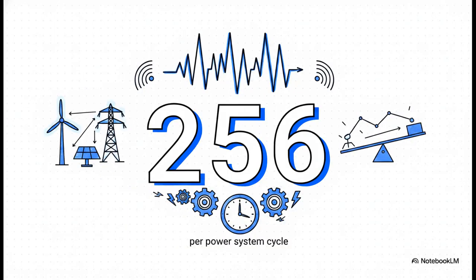To really give you an idea of just how precise this digital network is, consider this number: 256. In this architecture, those merging units can sample data at an incredibly high rate of 256 samples per power system cycle. Not per second, per cycle. That is the level of high-frequency, high-resolution power quality monitoring required to keep a lightweight, renewable-dominated grid from tipping over.